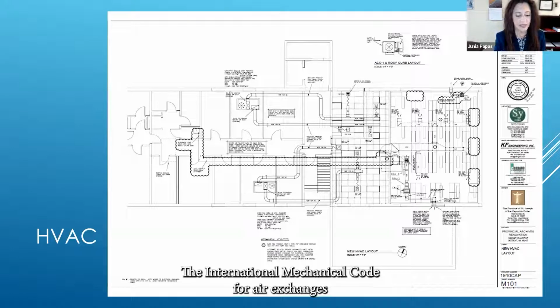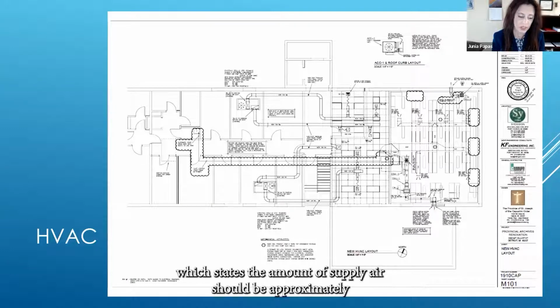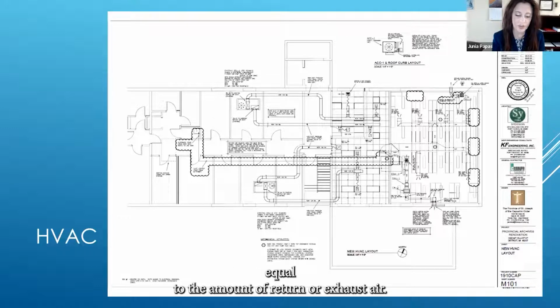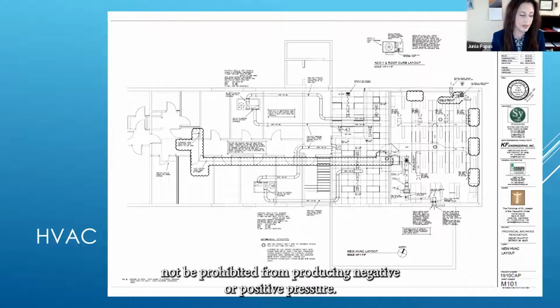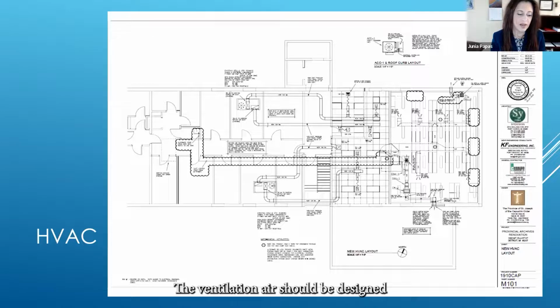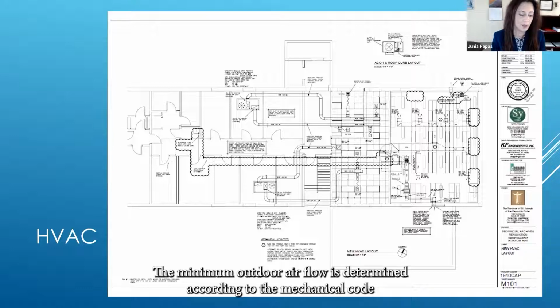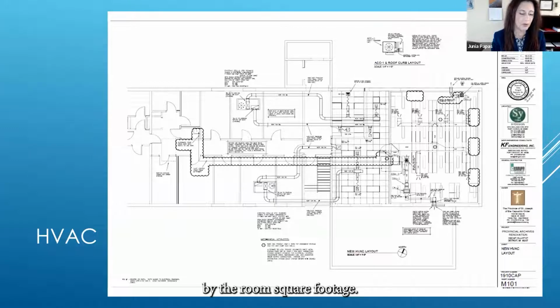The International Mechanical Code for Air Exchanges by Mechanical Means are outlined in Section 403, which states the amount of supply air should be approximately equal to the amount of return or exhaust air. The system shall not be prohibited from producing negative or positive pressure. The ventilation air should be designed and installed in accordance to this code. The minimum outdoor airflow is determined according to the mechanical code by the room's square footage.